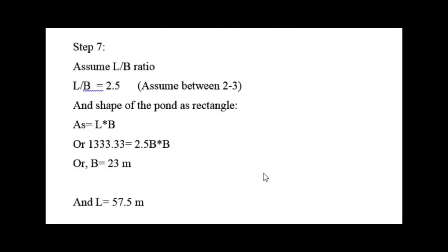In Step 7, we assume the pond is rectangular with a length-to-breadth ratio of 2.5 (within the acceptable range of 2 to 3). Using surface area = L × B = 2.5B × B = 1333.33 m², we get breadth B = 23 m and length L = 2.5 × 23 = 57.5 m.